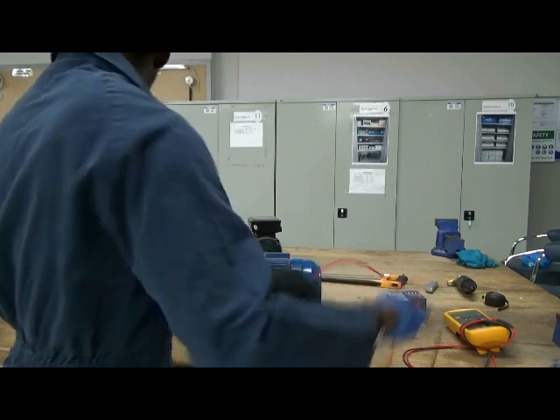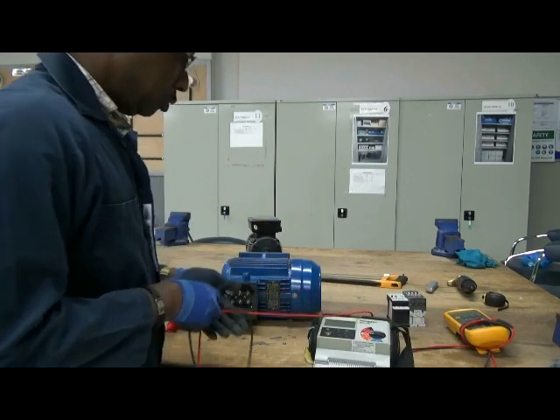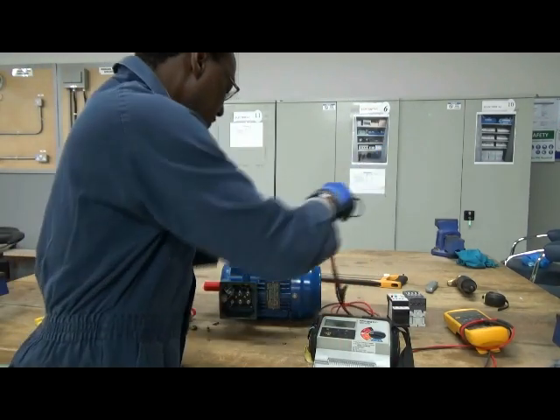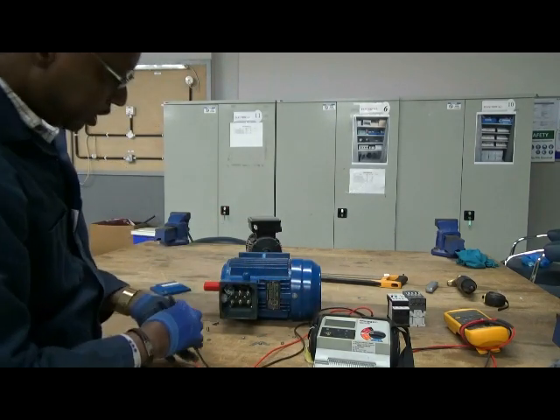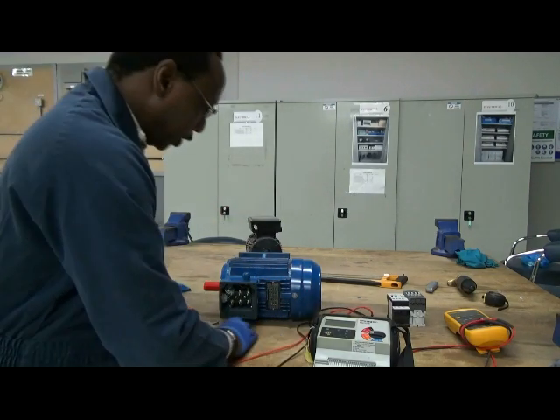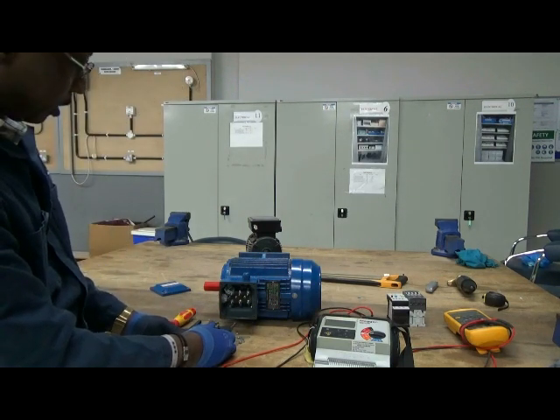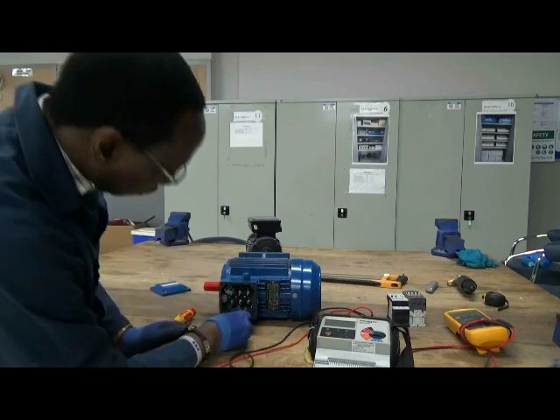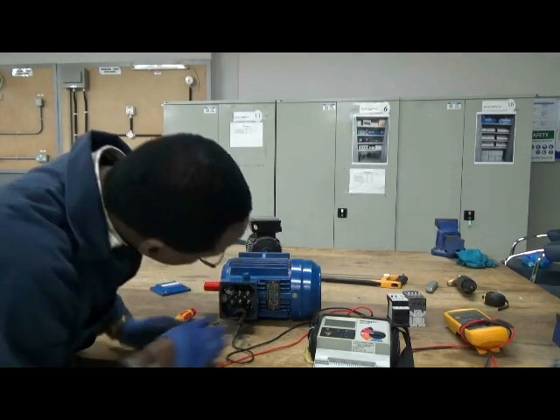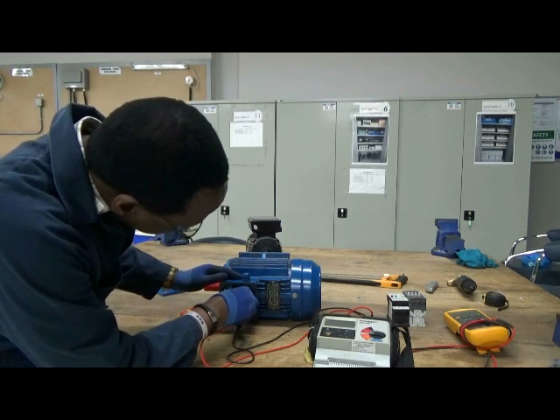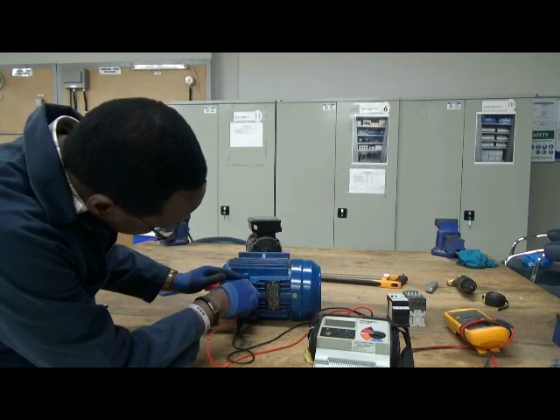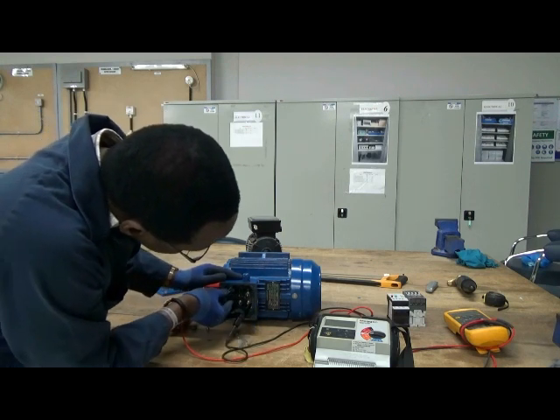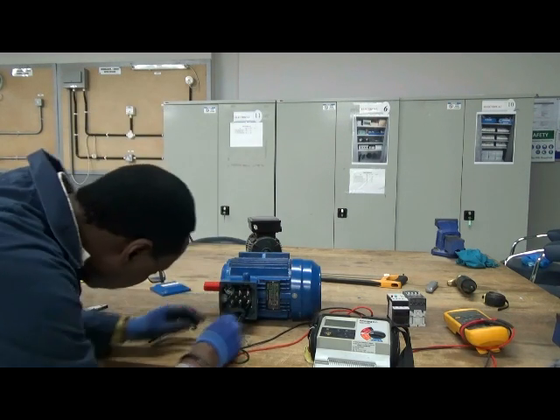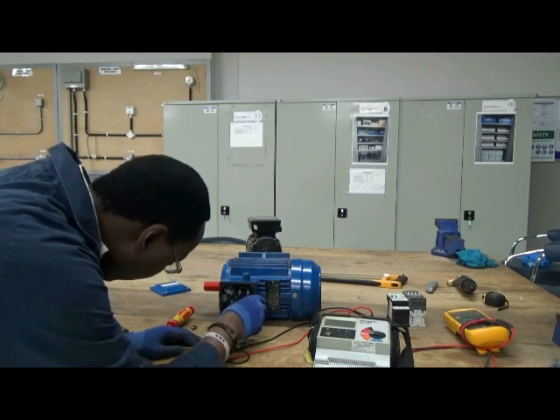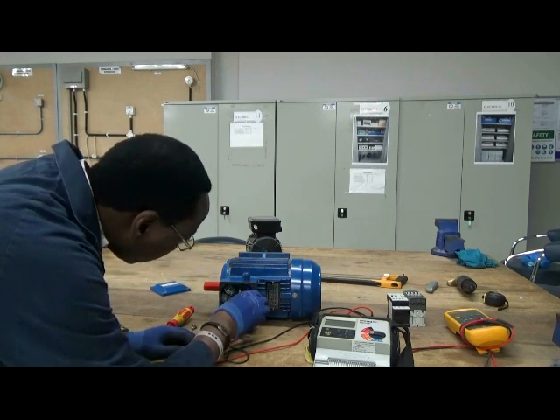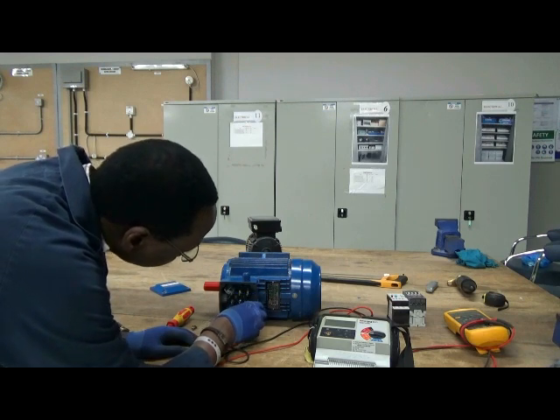The insulation resistance tester is an instrument used to test insulation resistance. So we want to see if all the windings are separate from each other, and also that they are separate from the earth or from the body of the machine. So I'll connect one point here first, and then on top of it I'll connect another probe. As you can see, I'm using crocodile clips. When I was using my multimeter, I was just holding the probes with my hands, and there was no problem.